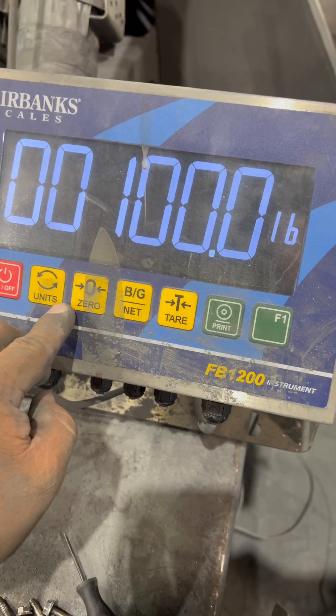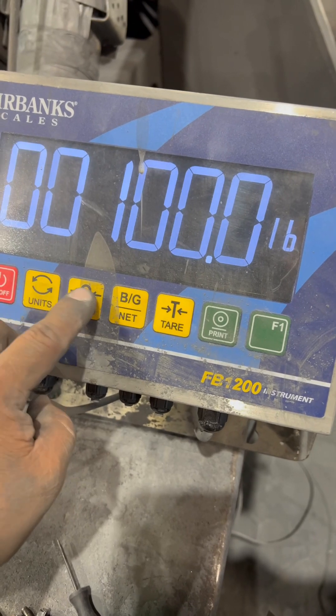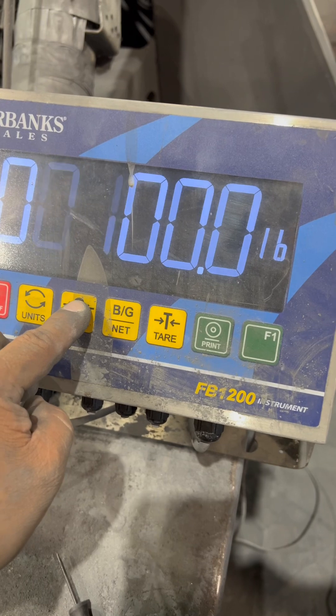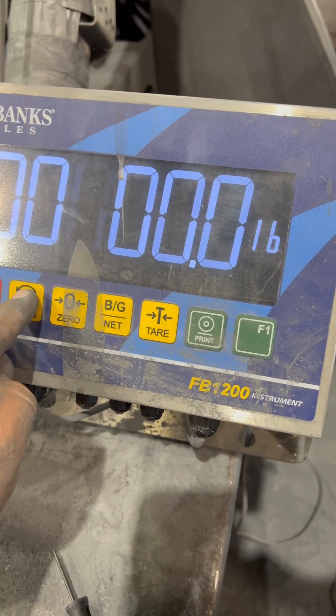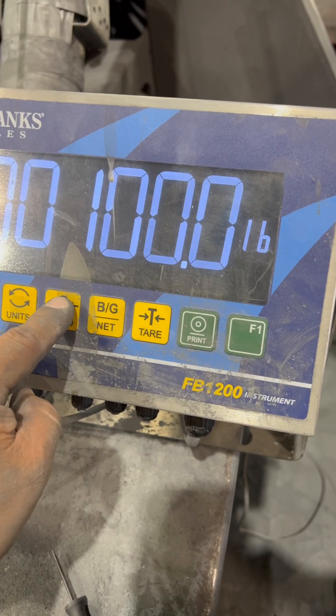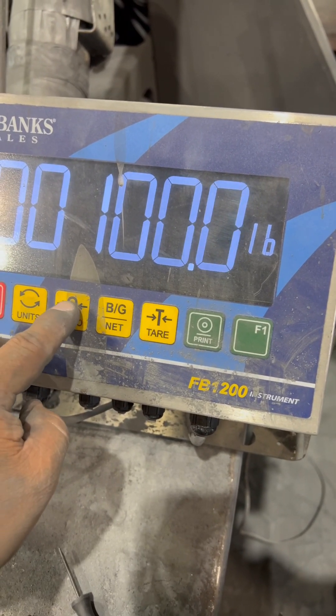Now what you want to do is put in the amount of weight you're using. The zero key moves the digit over. The gross/net key is decrease, and the units key is increase. So you get it to where you want, then use the zero key. Once that last digit is flashing, you hit zero again.